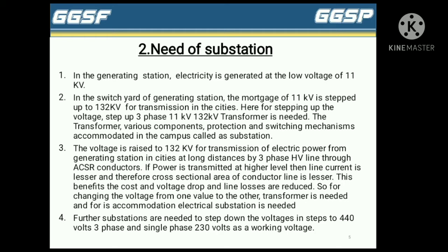In the generating side substation, the voltage is raised to 132 kV for transmission of electrical power from generating station to cities at long distances, by three-phase high voltage line through ACSR — Aluminum Conductor Steel Reinforced cables. If power is transmitted at a higher voltage level, then line current is lesser, and therefore the cross-sectional area of the conductor is lesser. This benefits the cost and voltage drop, and also line losses are reduced.